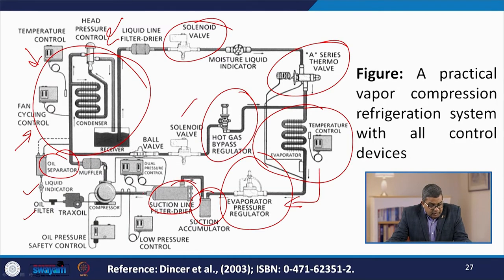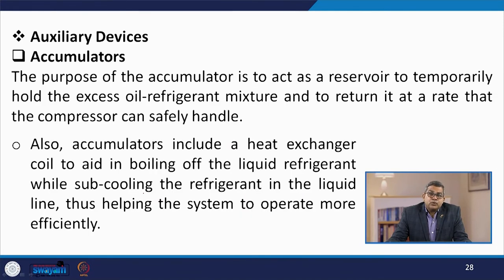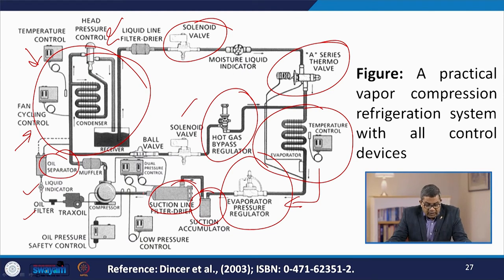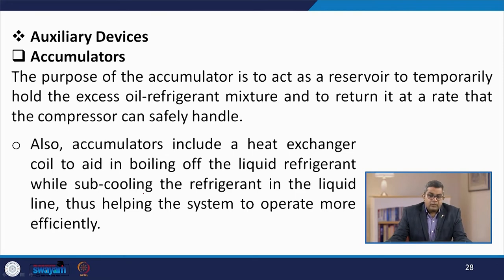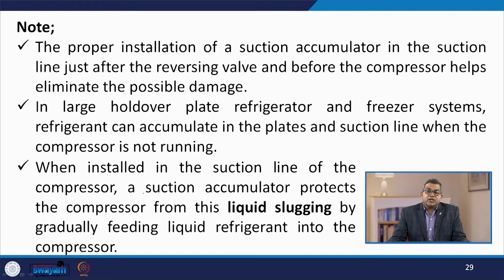When we talk about auxiliary devices, there are various types like accumulators and different types of valves. The purpose of an accumulator is to act as a reservoir to temporarily hold excess oil-refrigerant mixture and return it at a rate the compressor can safely handle. Accumulators also include a heat exchanger coil to aid in the boiling of liquid refrigerant while subcooling the refrigerant in the liquid line, helping the system to operate more efficiently. Proper installation of a suction accumulator in the suction line just after the reversing valve and before the compressor helps to eliminate any possible damage.